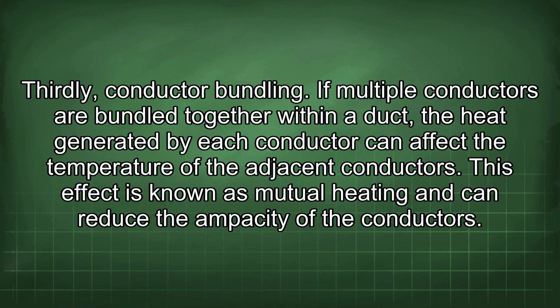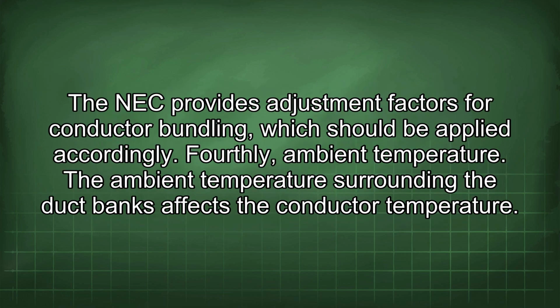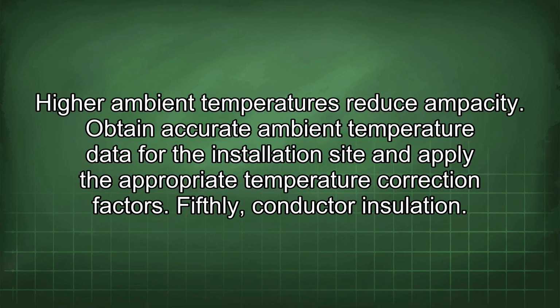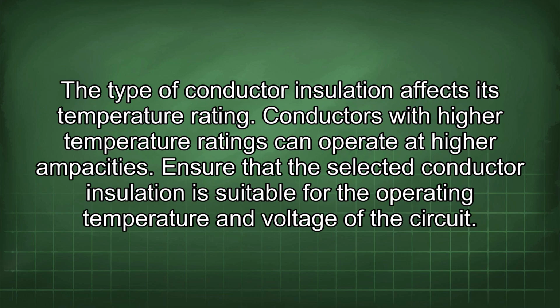Thirdly, conductor bundling. If multiple conductors are bundled together within a duct, the heat generated by each conductor can affect the temperature of the adjacent conductors. This effect is known as mutual heating and can reduce the ampacity of the conductors. The NEC provides adjustment factors for conductor bundling, which should be applied accordingly. Fourthly, ambient temperature. The ambient temperature surrounding the duct banks affects the conductor temperature. Higher ambient temperatures reduce ampacity. Obtain accurate ambient temperature data for the installation site and apply the appropriate temperature correction factors. Fifthly, conductor insulation. The type of conductor insulation affects its temperature rating.